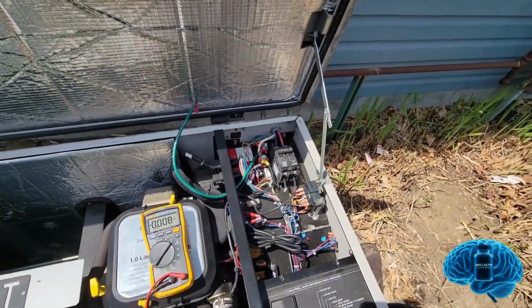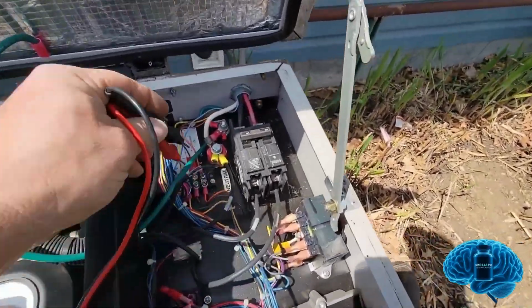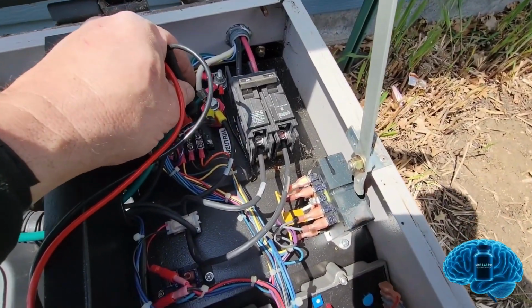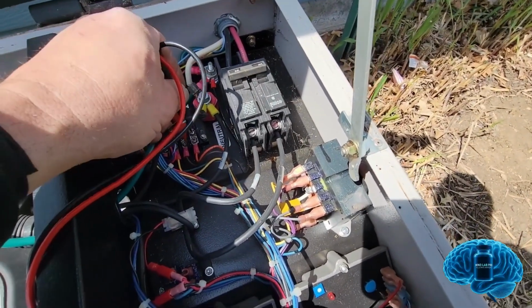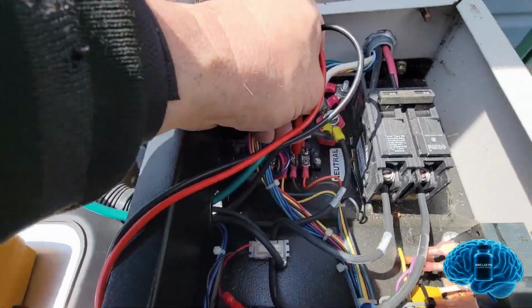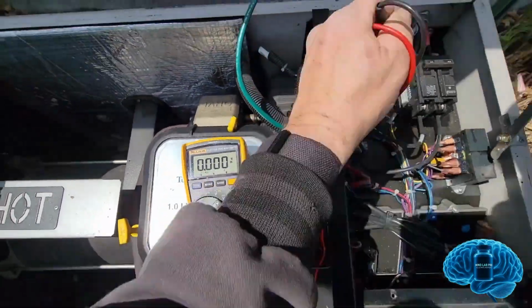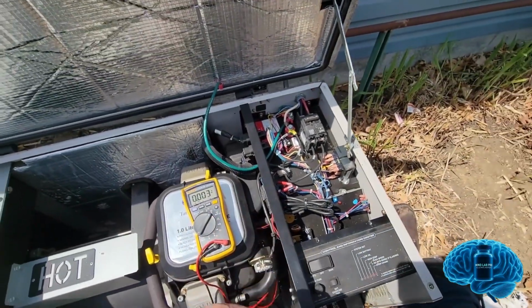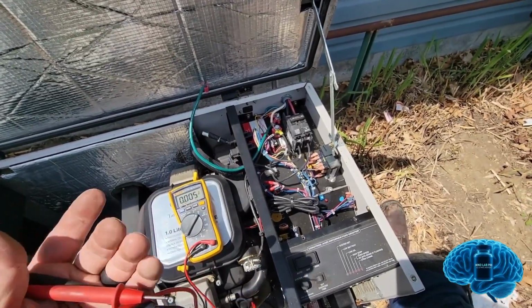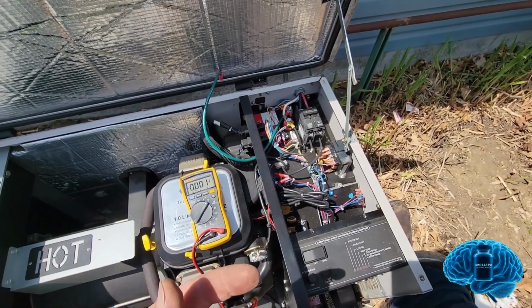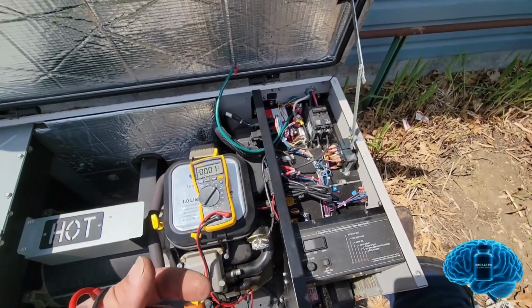So anyhow, yeah, we've got it there. Now if you check between the two of them, you won't have anything. So we go between those two and we have zero. When we trip this thing out, it should show 13 or so volts, and that's going to power the transfer switch, and you're going to see the motor bog down.